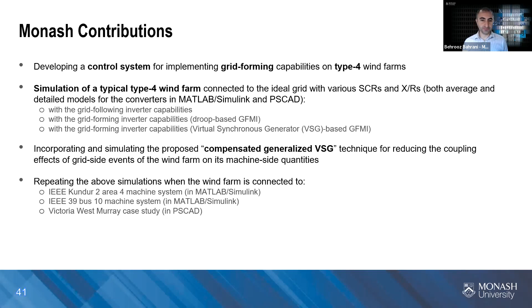the control system, the grid side converter. It does require to control the DC link voltage. It does require to control the rotor speed, and obviously provide all the services that you would require as a VSG. So the primary loop here, voltage loop and current loop, are pretty similar, but still there are certain differences between these blocks and a normal VSG, but the capability is the same. So it can provide inertia, it can provide the damping that you require, and it doesn't require any PLL to be connected to the grid.